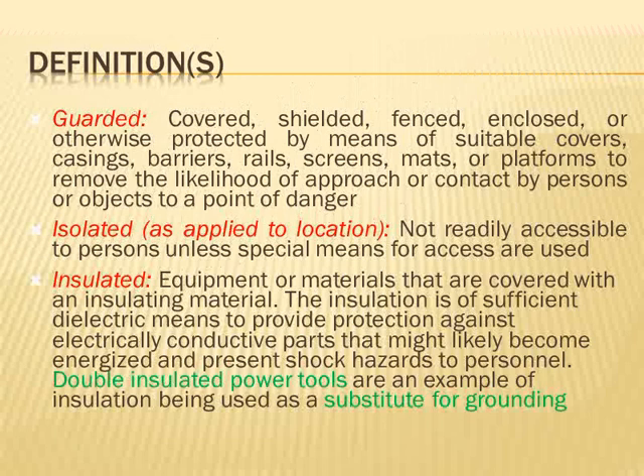So isolated, guarded, you cover it, shield it, fence it, or isolate it, not readily accessible. And insulated, you double insulate like tools and equipment. These are alternatives for grounding the equipment. I can think of your electronic equipment will be isolated, even though it's still grounded with its own grounding, but it's isolated from the ground though.